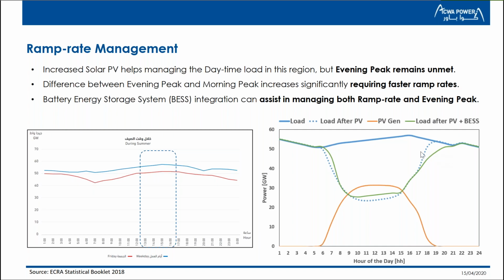PV takes care of the daytime load, but there are 3 points which need to be taken care of. Let's say 2. One is that the evening peak load still remains unmet. Second, when the PV generation drops down in the evening, let's say from 5 to 7 p.m., the ramp rate required by non-PV generation assets is very steep, which creates a strain on the network and on the power plants as well. Now, if we add BESS to a PV power plant, the expected load curve.